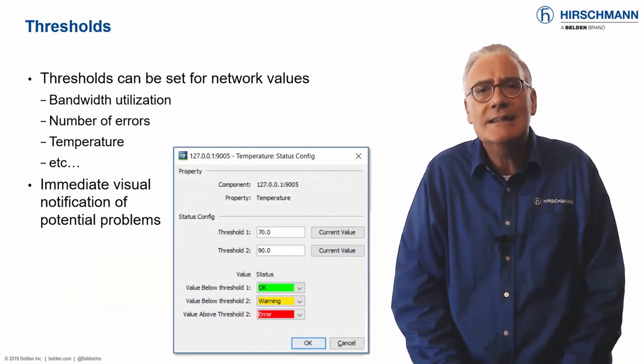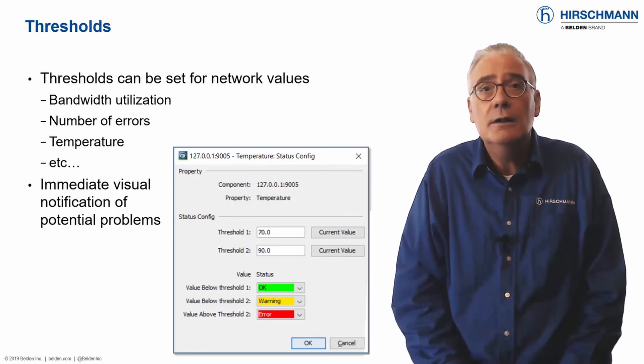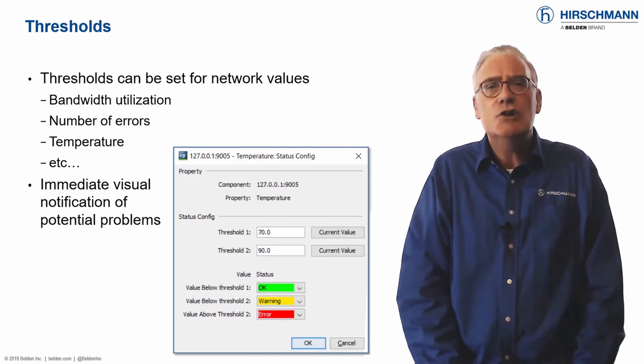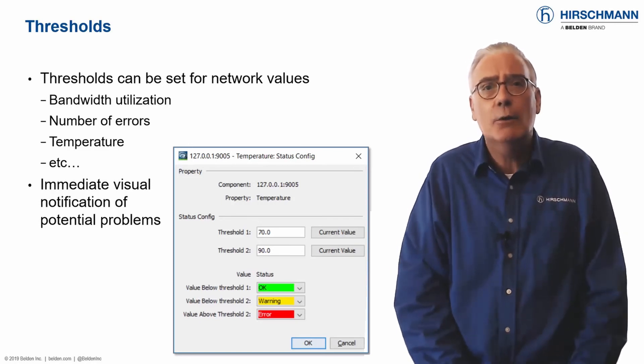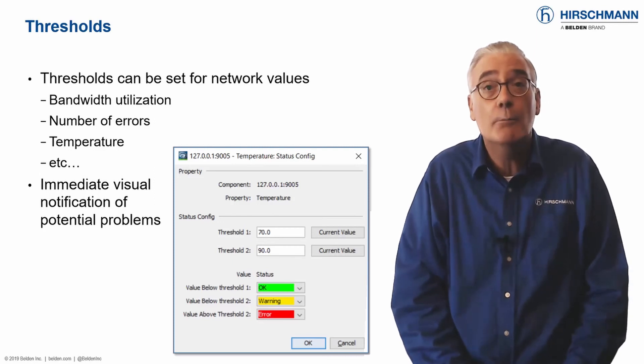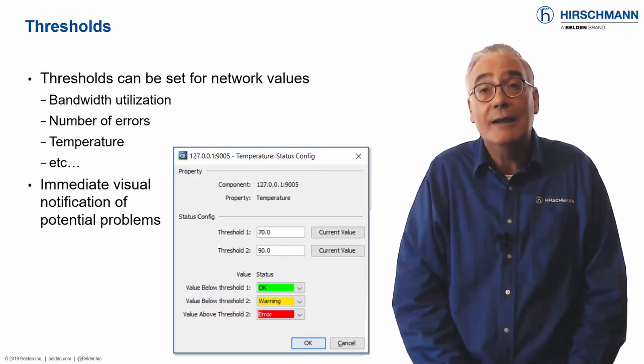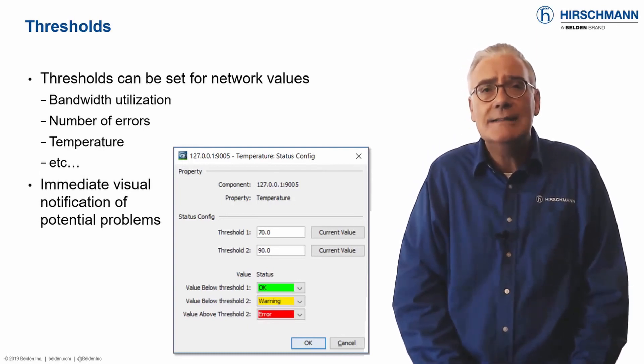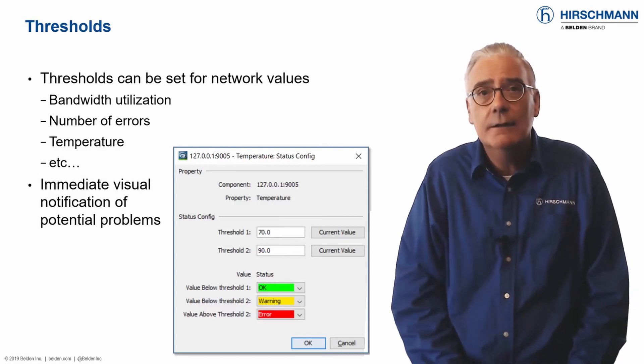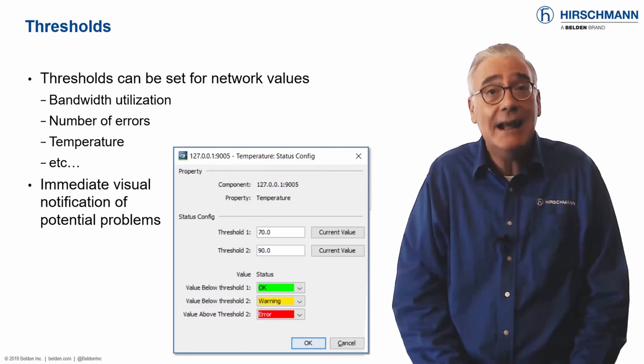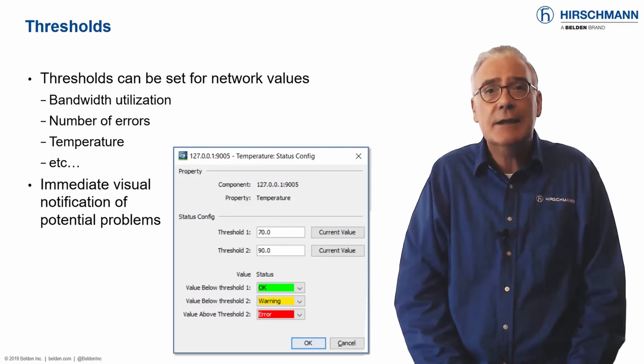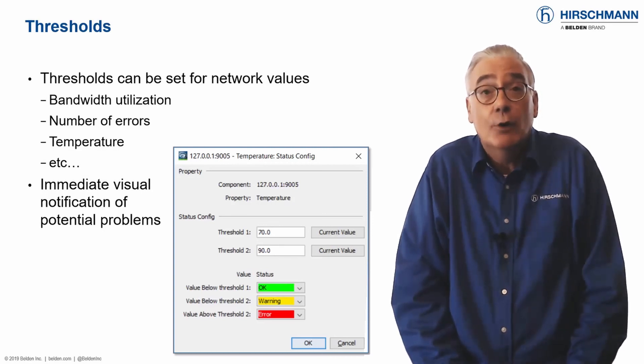As a network administrator, you need to be aware of changes which occur on your network. Physical changes are easy to spot because they will immediately be highlighted in your network management system. Changes in other characteristics are less obvious but can be just as catastrophic. OT networks tend to have predictable traffic patterns based on polling, so changes in network load happen for a reason and must be investigated. If a connection is experiencing an increasing number of errors, this indicates the likelihood of future failure. Increases in device temperature could indicate a cooling failure. Thresholds can bring these and many other conditions to your attention by generating alarms, giving you breathing space to react and potentially avoid a major incident.